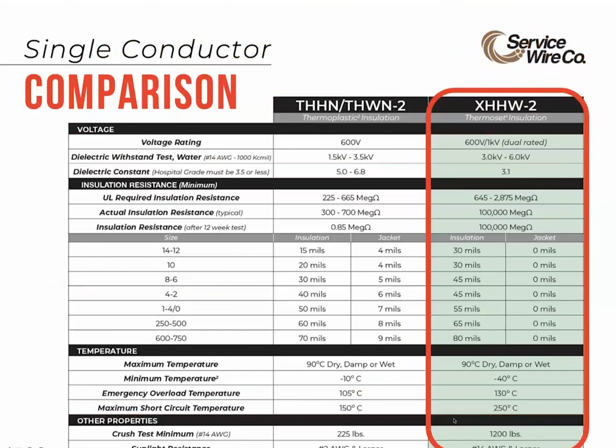XLPE products like Service Wire's XHHW-2 pictured here, and USE and RHW, are made with cross-linked polyethylene instead of PVC nylon. Thermoset insulation is more resistant to chemicals and abrasions and far less toxic than PVC thermoplastic insulation in the event of a fire. Thermosets are also more resistant to leakage current and have far superior electrical performance.